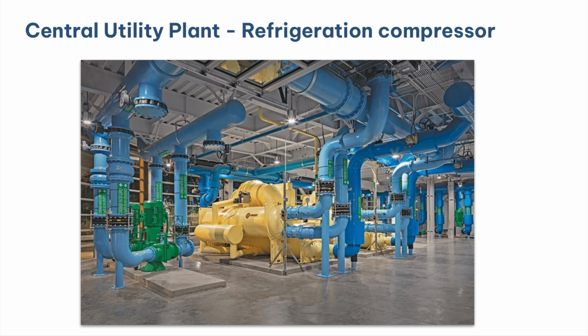So an operator could set the conditions and then go take data with their portable system and make sure they're taking data in the same state every single time they collect. Their failure mode is also relatively slow compared to other systems, so it does take a while for a failure to develop. But if you wanted to, you could use an MVX or an online system on here because it would allow for the changing state and speed of the compressor that would give you actionable trends and data.